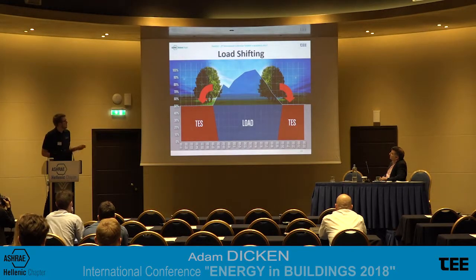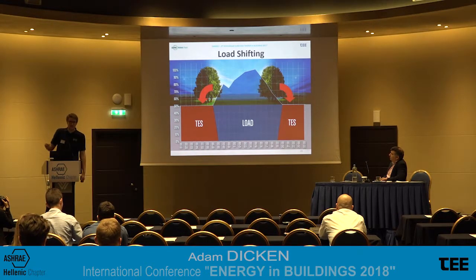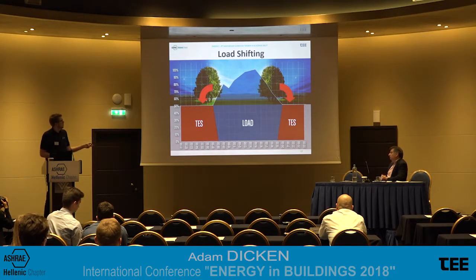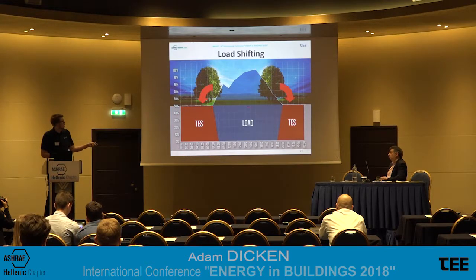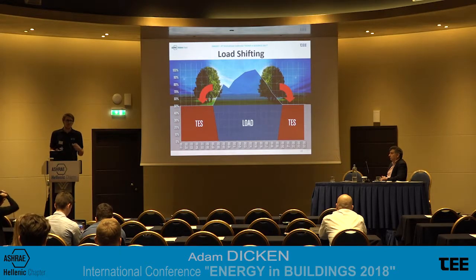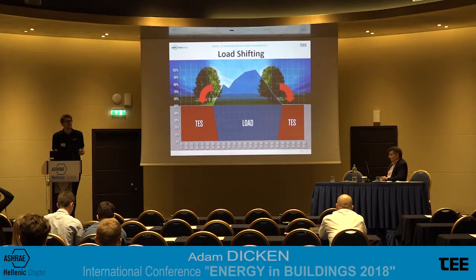To show this load shifting graphically, you can have a peak potentially in the middle of the day when the sun's bearing down, your COP is not very good, and your electrical costs are high. What we're able to do is shift that load and turn it into a flat line, or there are many different load profiles you could attempt to go after. You could even shut off your system entirely if you wanted to, but I wouldn't really recommend it.